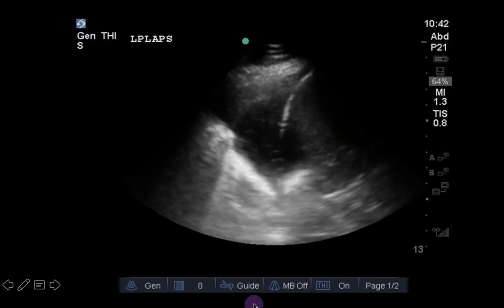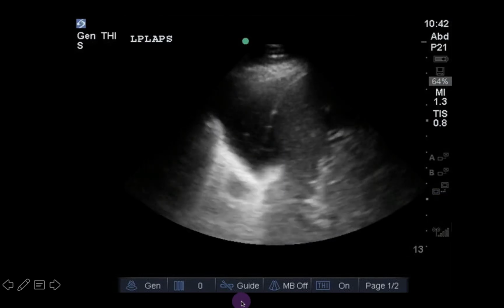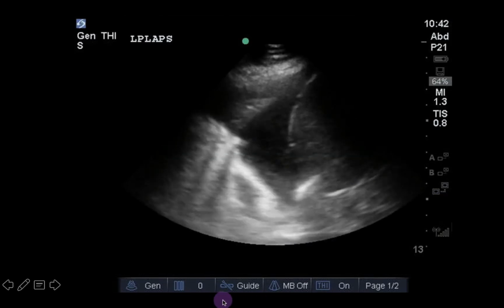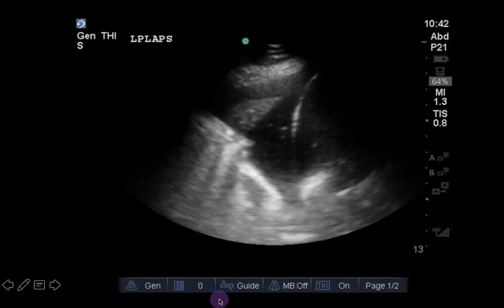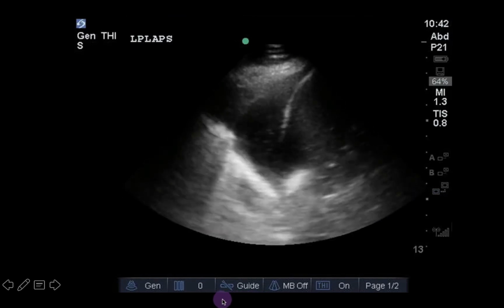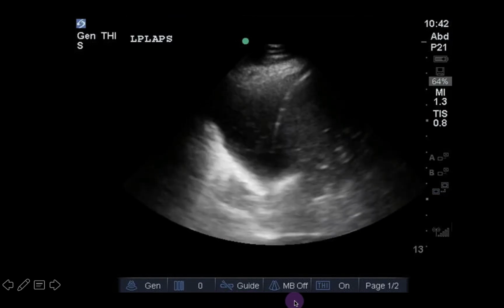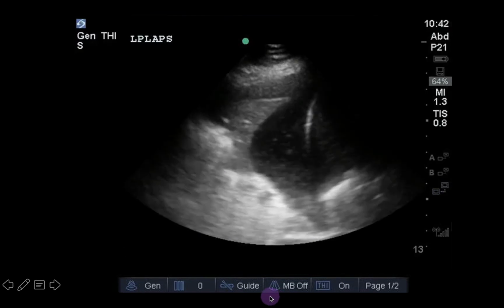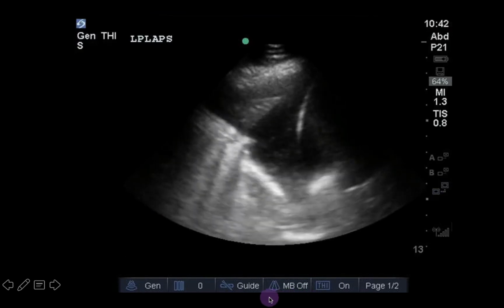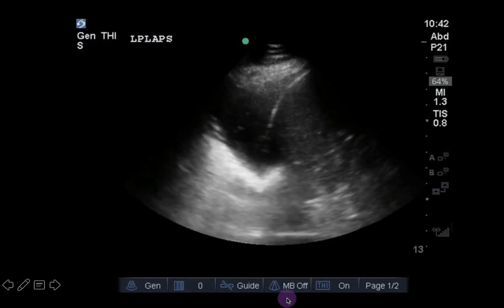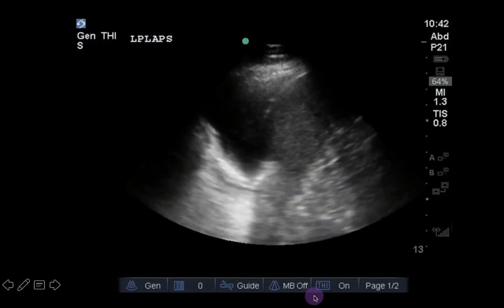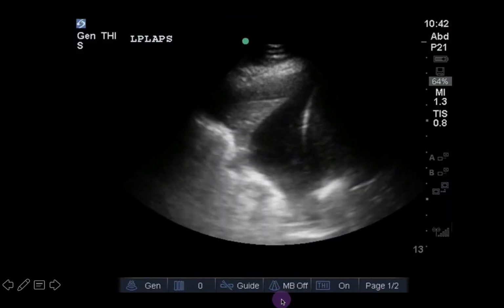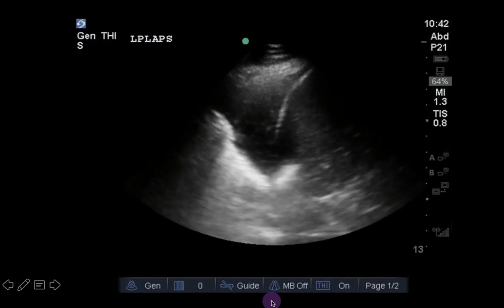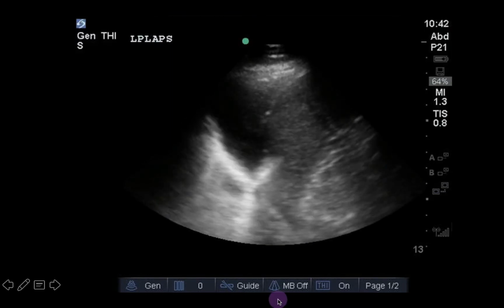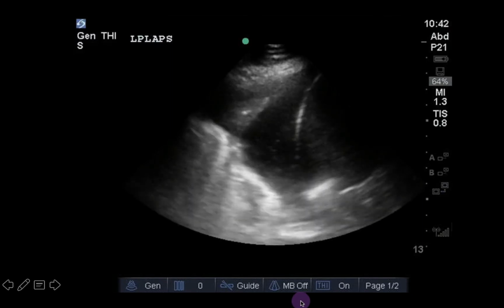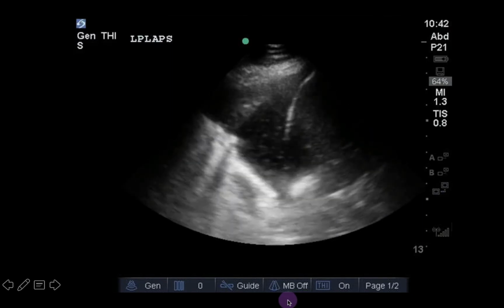The next button allows you to choose whether or not you want a guide in the center of the screen. This is used for ultrasound guided procedures. The next button is multi-beam. This function makes the probe send out multiple beams at multiple angles. It helps you see around corners and reduce artifacts from echoic structures in the near field. Understandably, this should generally be turned off for lung ultrasound when we are trying to bring out artifacts.